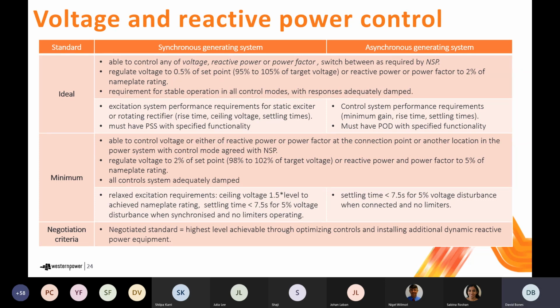So the next technical requirement is the requirement to provide control over voltage and reactive power. If you're meeting the ideal performance standard, then your large generating system must be able to regulate any of voltage, reactive power or power factor, and to switch between those control modes as required by the NSP. Furthermore, you have to meet regulation requirements. So you need to be able to regulate voltage to within 0.5% of a nominated set point, or reactive power or power factor to 2% of the nameplate rating.